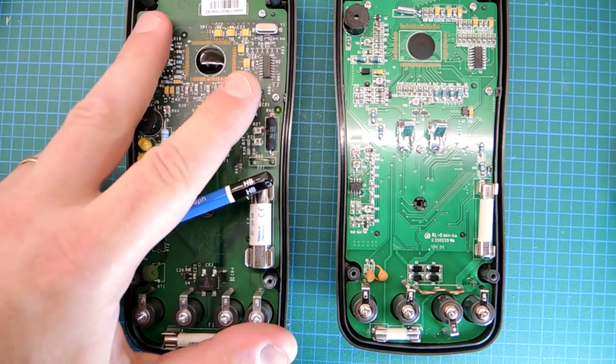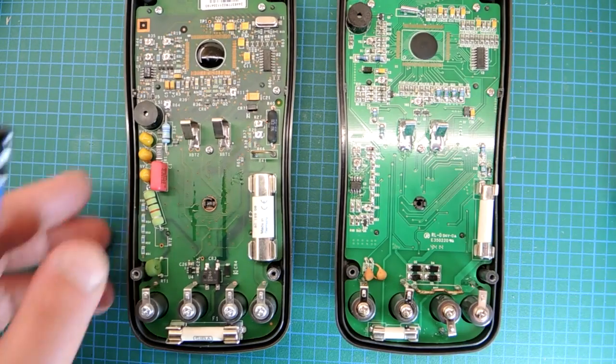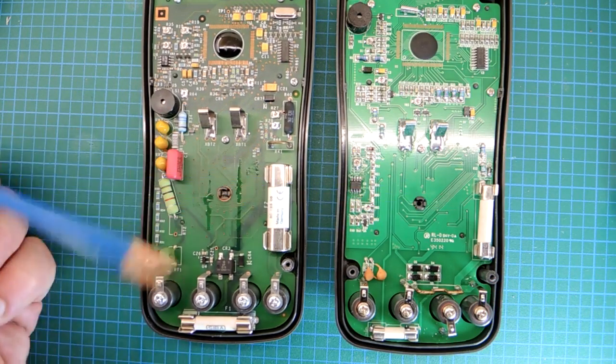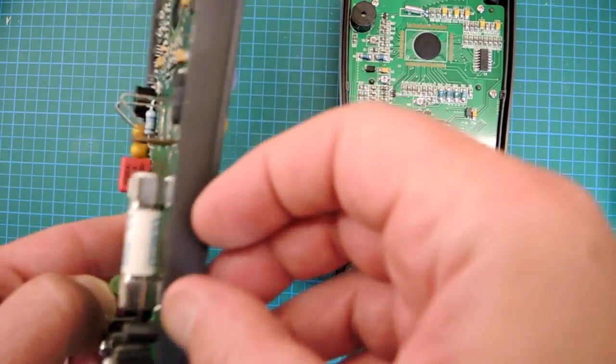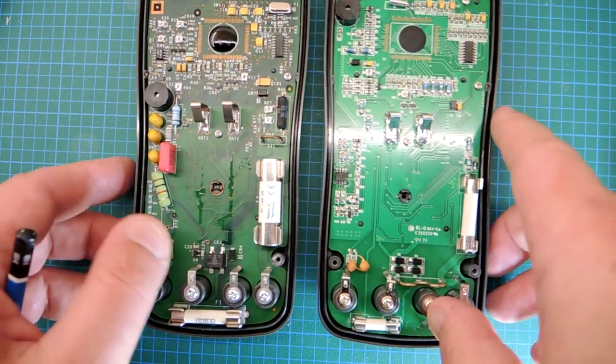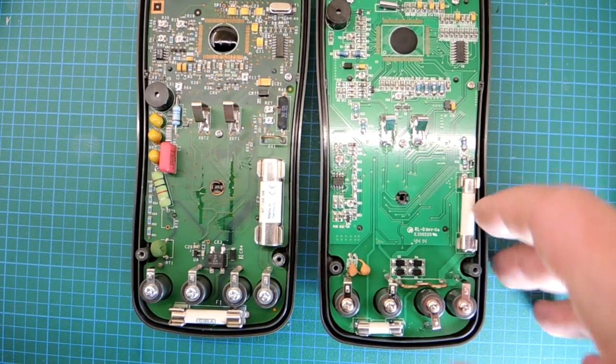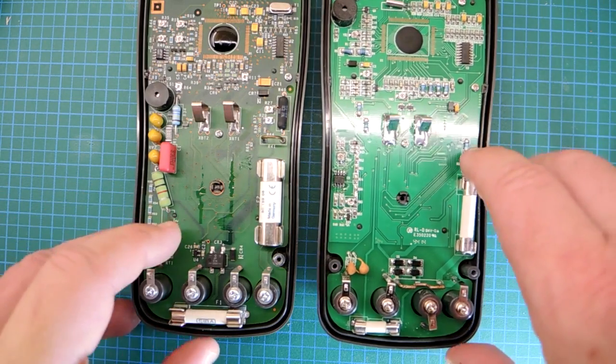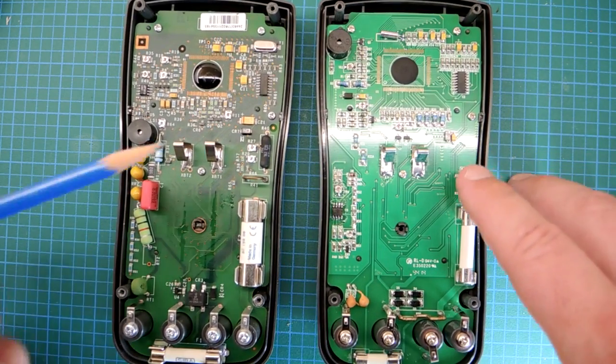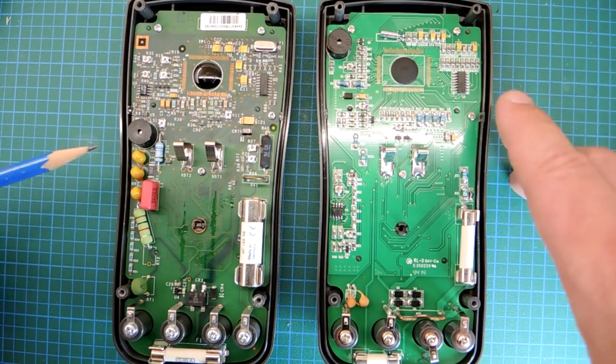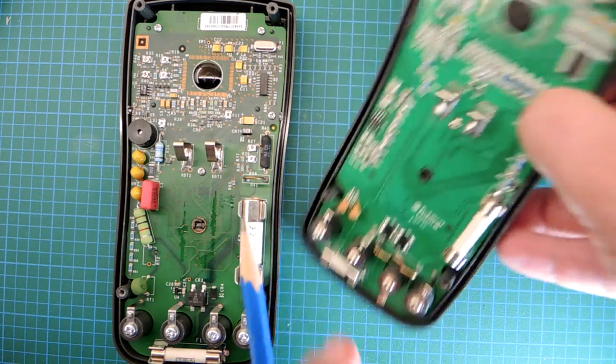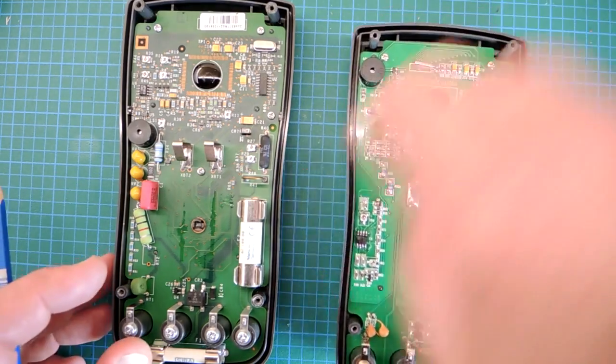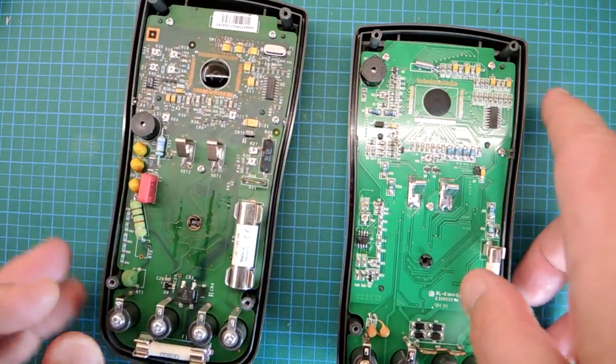Just opened up both meters. The Fluke meter is on the left here, and the AMO meter is on the right. You can quickly see that they're not the same circuit board, but there's some interesting sort of comparisons you can do. The fuses in the Fluke meter have markings on them. In fact, this one's a German-made fuse. There's sort of a traceability to the fuse, so you have some confidence it meets its requirements. This looks like a ceramic fuse, but there's absolutely no regulatory markings on it whatsoever, so there's no traceability. That's a big concern with the really inexpensive meters as to whether or not they're very safe to use on high-energy circuits.